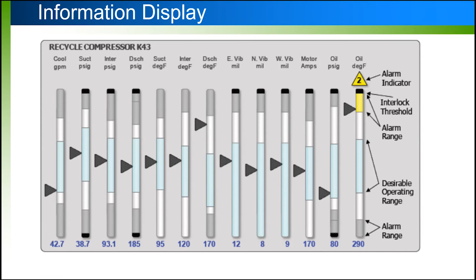Let's go into more detail on this type of information display. Starting on the left-hand side, we see the value displayed down on the bottom in blue, so if you need to know the exact value, you have it, but we also have its normal range and current value, so where it's sitting within that range you can see very quickly. The white color denotes it's in the abnormal range, but it's not an alarm, so it's okay to be there, it's not an issue, but it's normally not there. Then you have your alarm ranges, high and high, low and low, and even an interlock function.